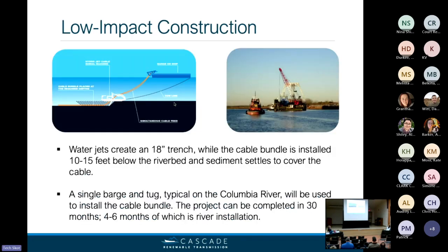This slide indicates how, with a surface laying mechanism through a barge type system, we will be on the surface of the river. We will have a full reel of cable for each of the 2 conductors located on the barge. From there, as shown in the previous picture going off the back end of the barge, the cable is held in catenary down to something called a hydroplow.